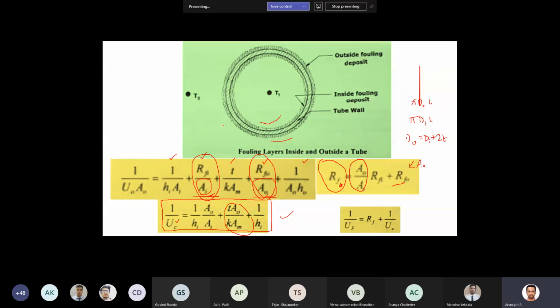Okay, so initially we cannot do this, because to calculate the film coefficient, we need the dimensions of the exchanger. Film coefficients are normally calculated, as I said yesterday, using the Sieder-Tate equation. If it is condensation, you have to use the Nusselt equation. These equations are empirical and dimensionless, involving your operating variables, the dimensions of the system and the fluid properties.